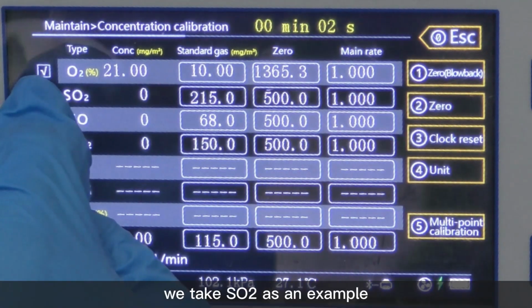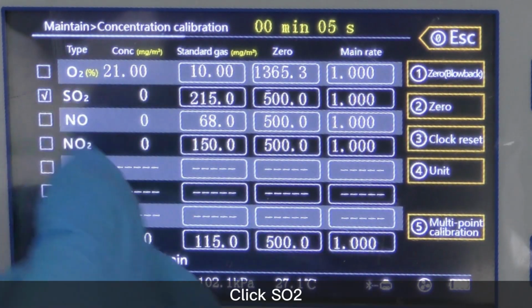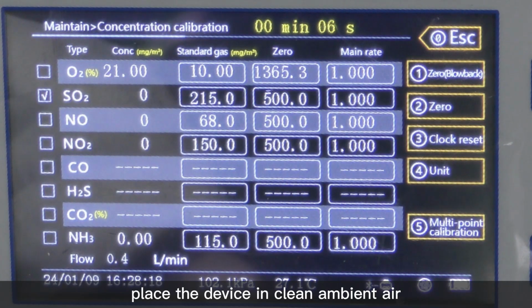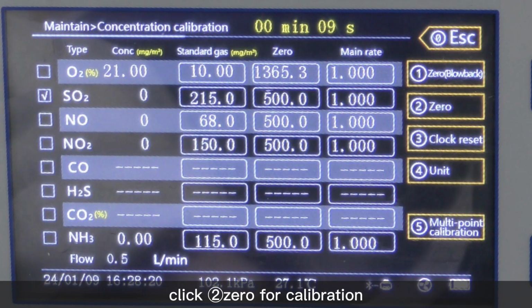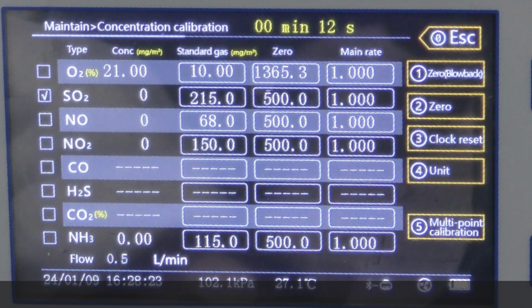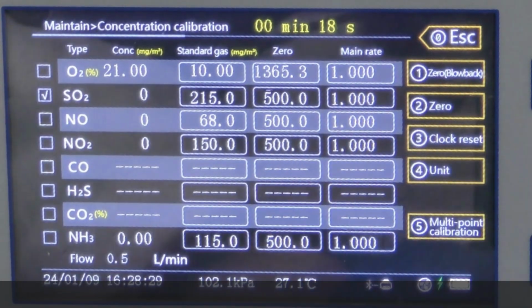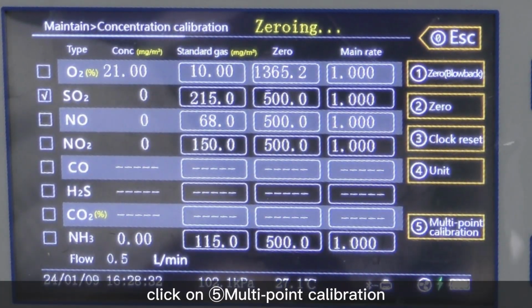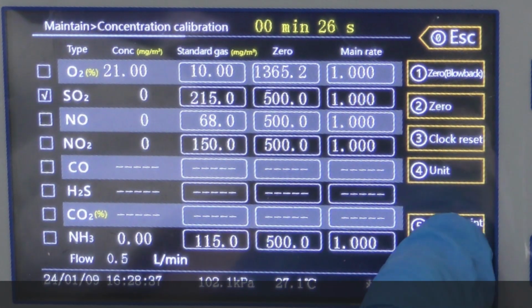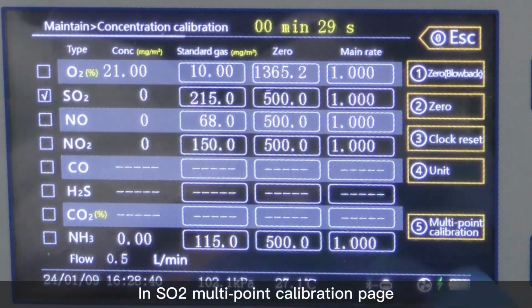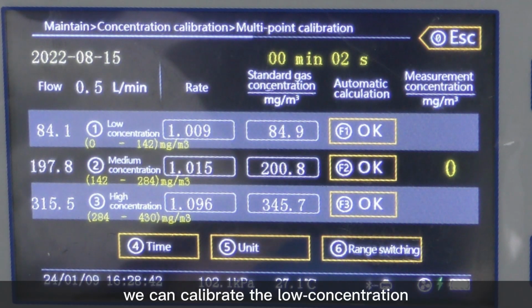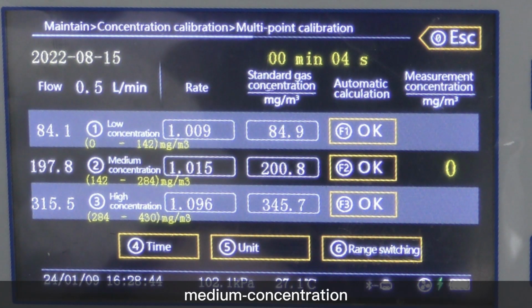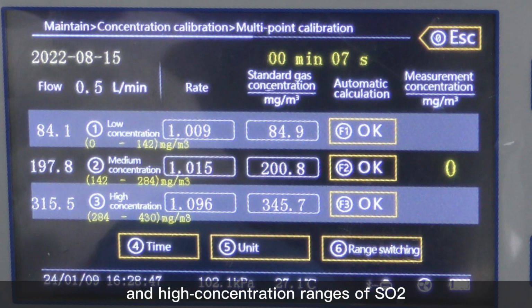Enter into concentration calibration interface. We take SO2 as an example. Click SO2, place the device in clean ambient air. After the data are stable, click zero for calibration. After zero calibration finish, click on multi-point calibration. In SO2 multi-point calibration page, you can calibrate the low concentration, medium concentration and high concentration ranges of SO2.